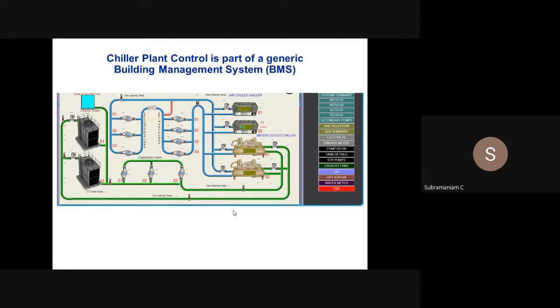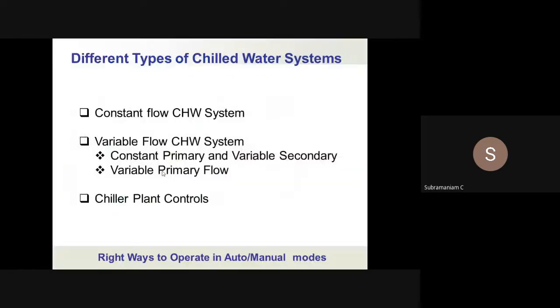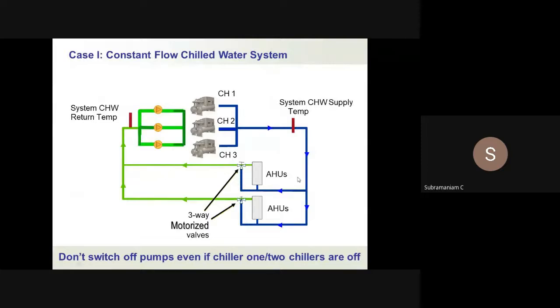So the graphic screen should depict whatever is installed, the way it is piped in the system at site. So you have chillers, you have primary pumps, secondary pumps, a decoupler line here, and cooling towers, condenser water pumps, and all that stuff there, right? So the constant flow, see, this is a constant flow system because you have a 3-way valve in the AHU. For example, healthcare, hospitals mostly follow the 3-way valve system, right? So 3-way valve system means constant flow, which means whether out of 3 chillers, for example, even if I switch off one chiller, all the 3 pumps have to work.